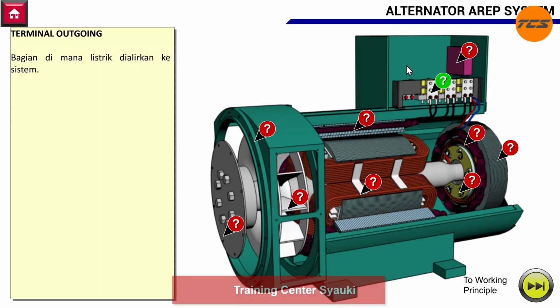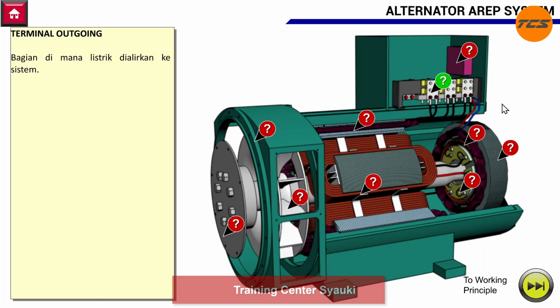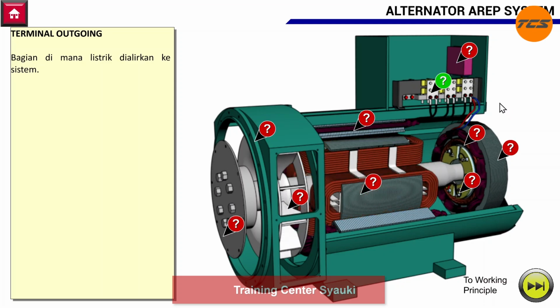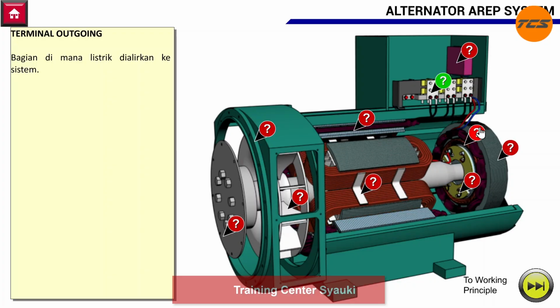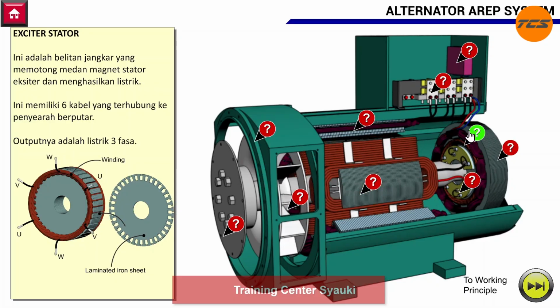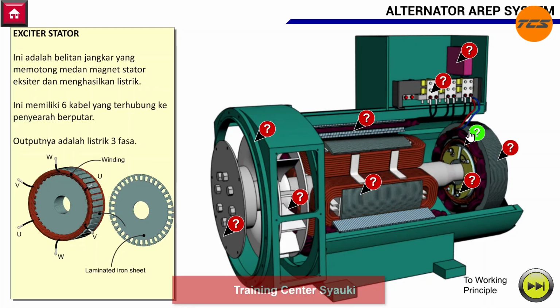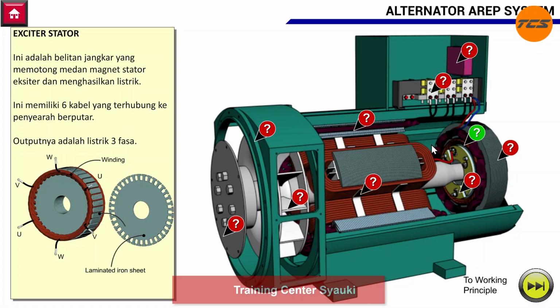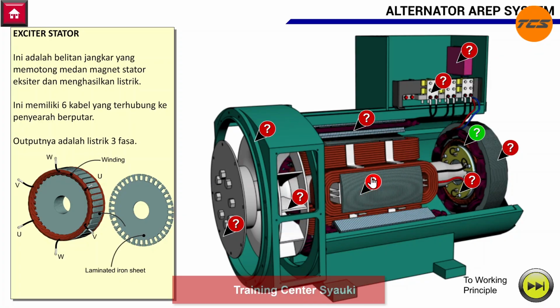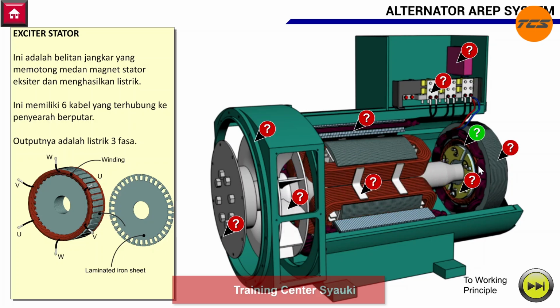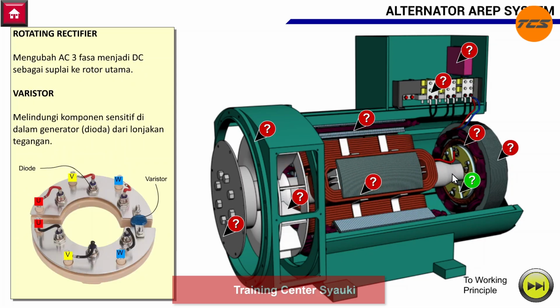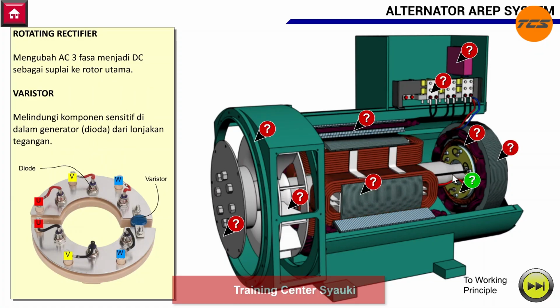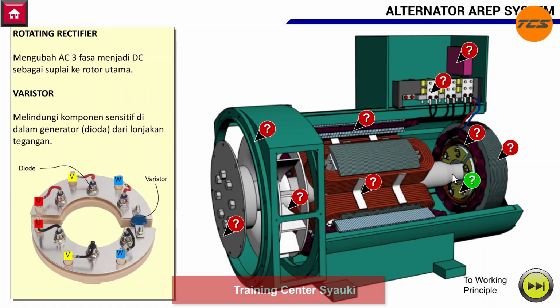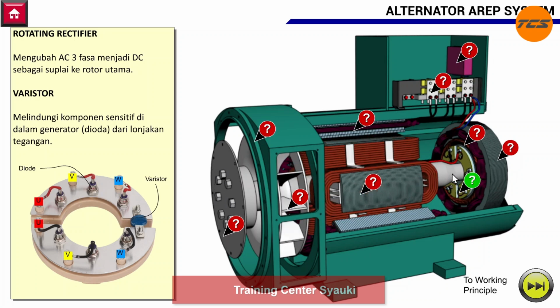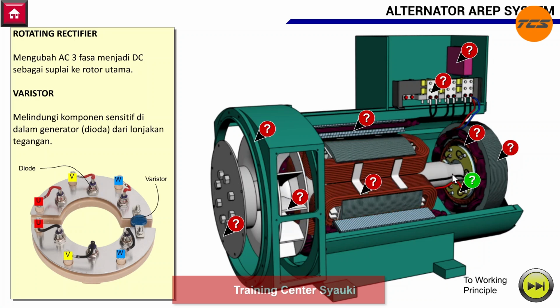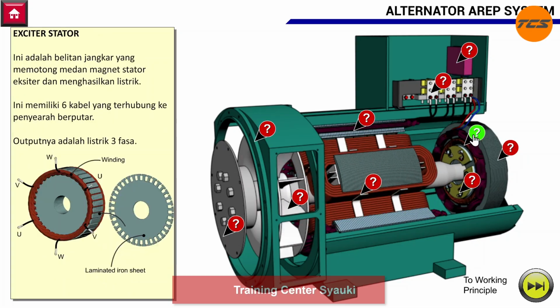Now we move to the exciter generator. The function of the exciter generator is to supply excitation voltage to the main rotor. The main rotor requires direct current to create a stable and controllable magnetic field. This DC current is supplied through a rotating rectifier. The rotating rectifier converts 3-phase AC electricity into DC electricity. Where does this 3-phase AC come from? It comes from the exciter's rotor.